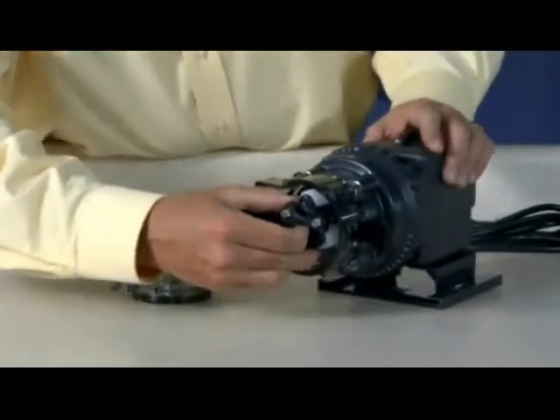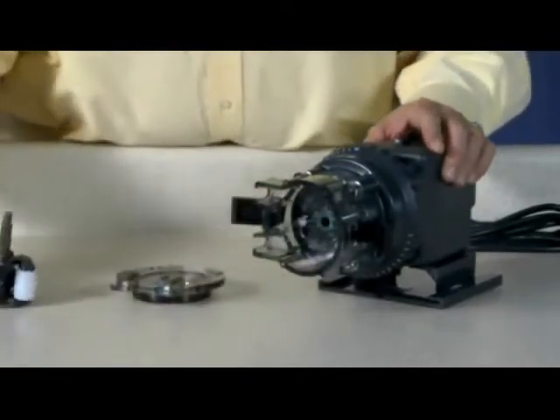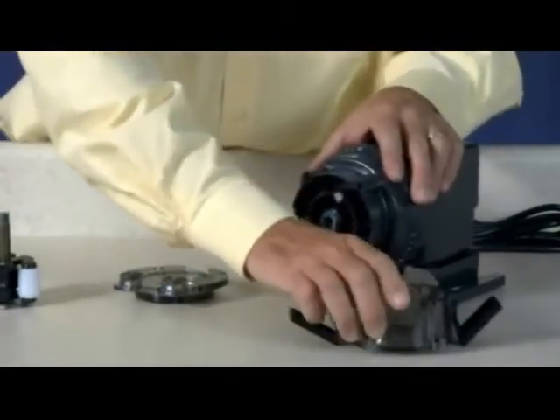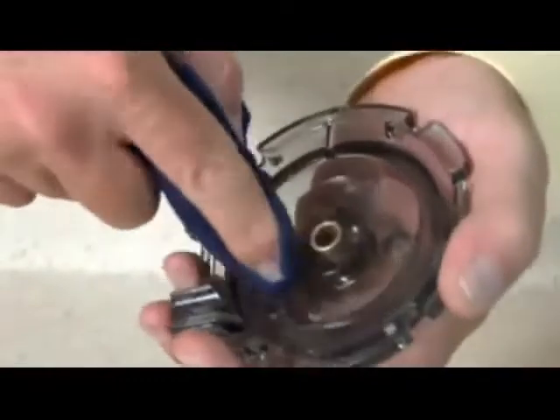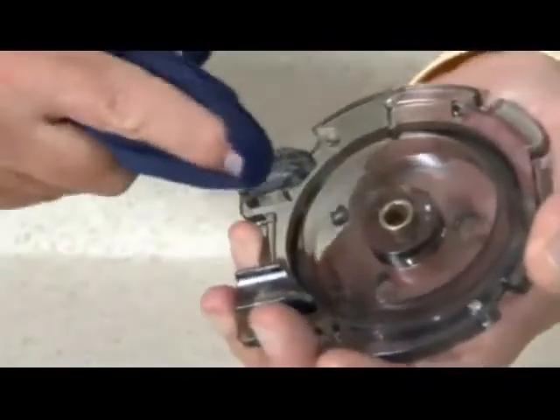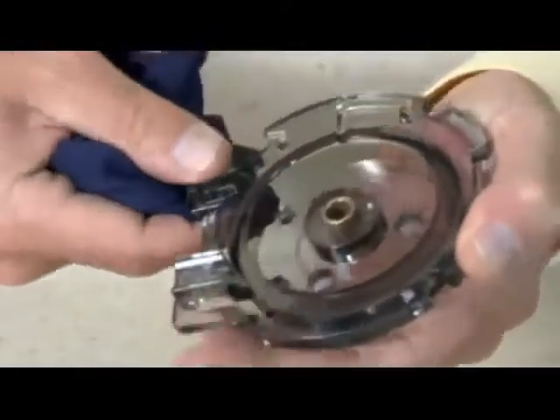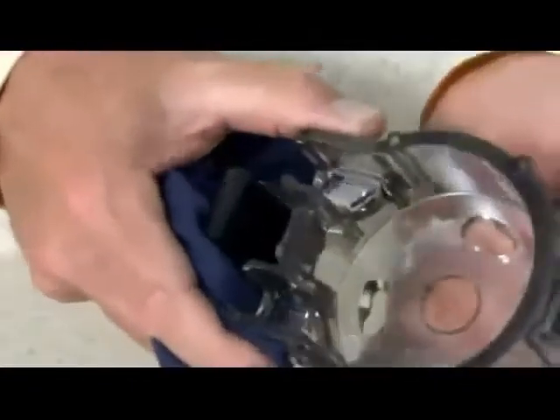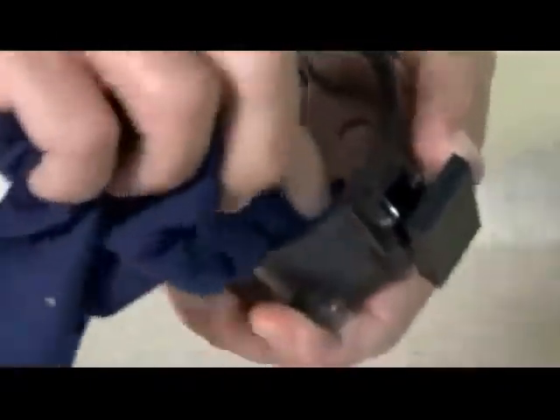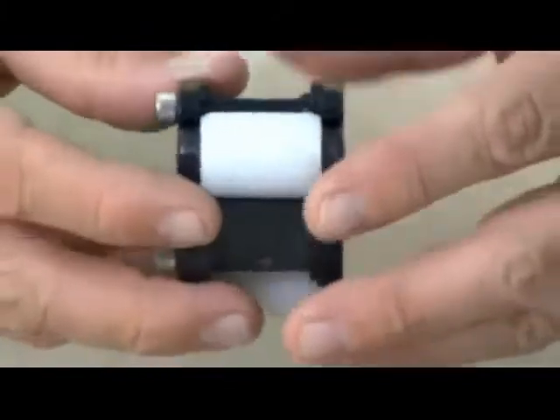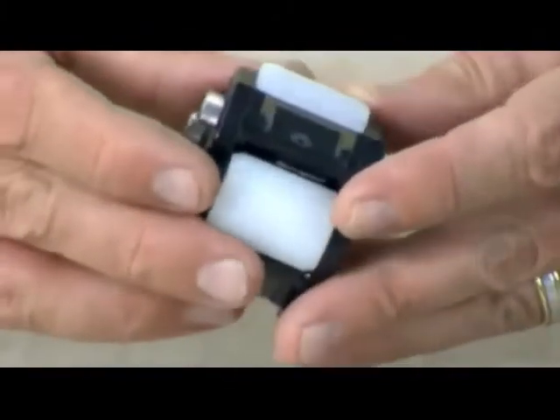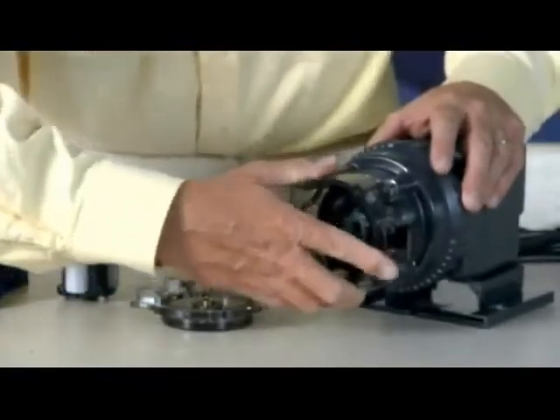Remove the roller assembly, the tube housing, and the shaft. Set them aside to reinstall later. Use a non-citrus all-purpose cleaner to clean chemical residue from the tube housing, roller assembly, and cover. Check the housing for cracks and replace it if it is cracked. Ensure the rollers turn freely. Replace the roller assembly if the rollers are seized or worn, or if there is a reduction or lack of output from the pump. Reinstall the clean tube housing.